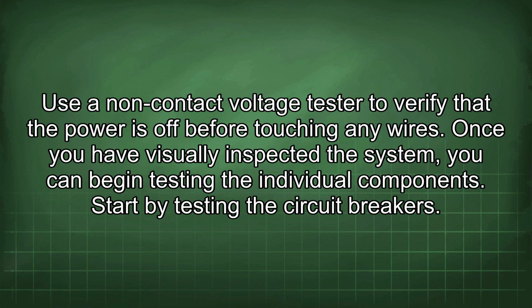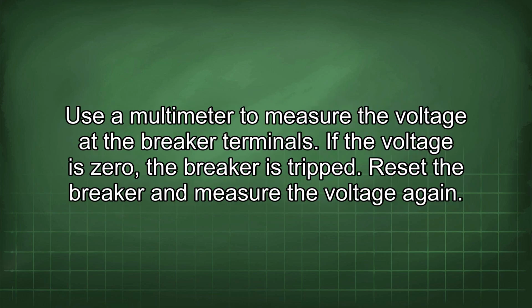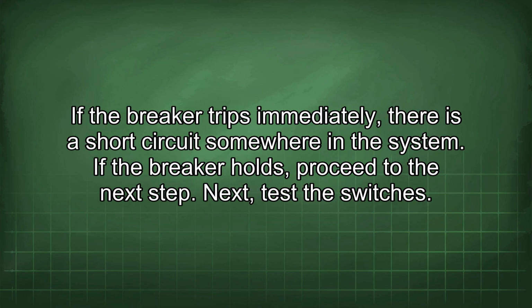Once you have visually inspected the system, you can begin testing the individual components. Start by testing the circuit breakers. Use a multimeter to measure the voltage at the breaker terminals. If the voltage is 0, the breaker is tripped. Reset the breaker and measure the voltage again. If the breaker trips immediately, there is a short circuit somewhere in the system. If the breaker holds, proceed to the next step.